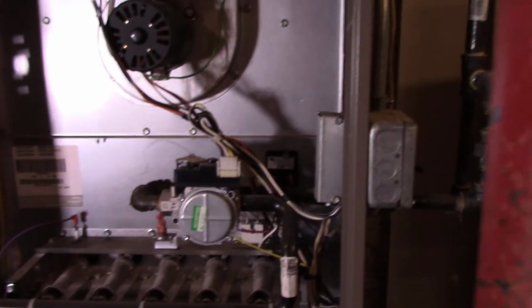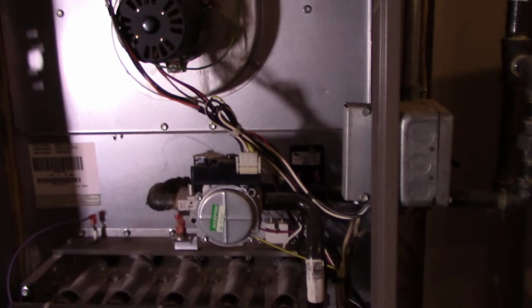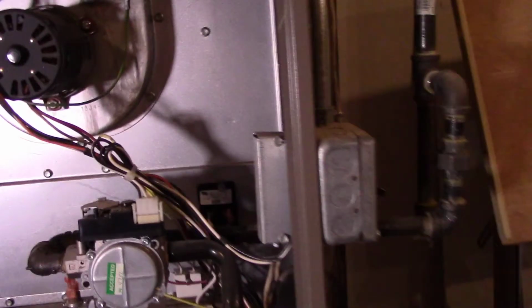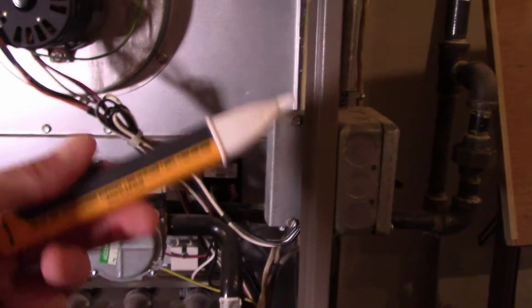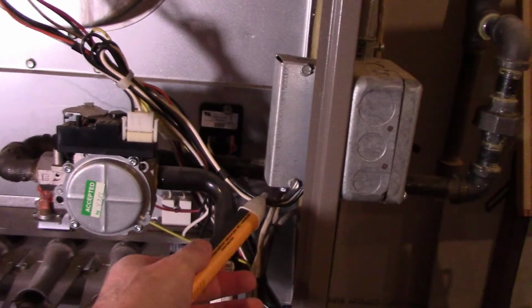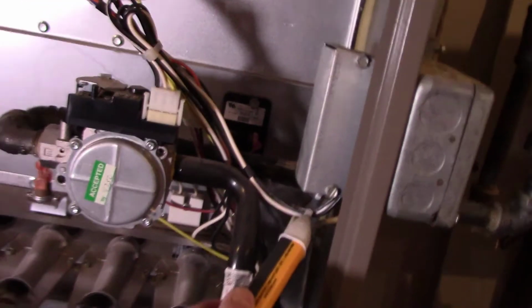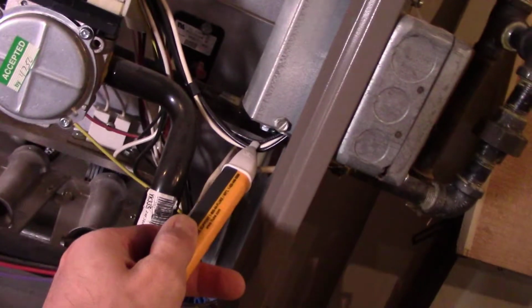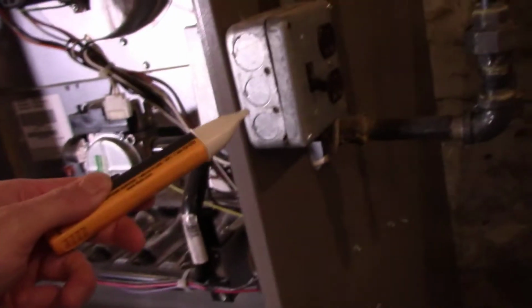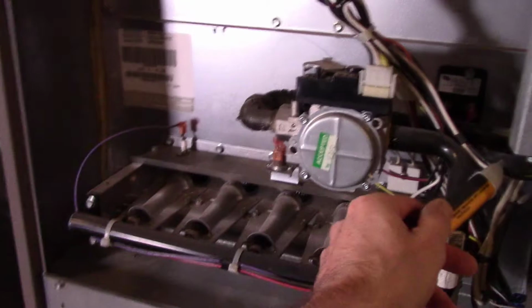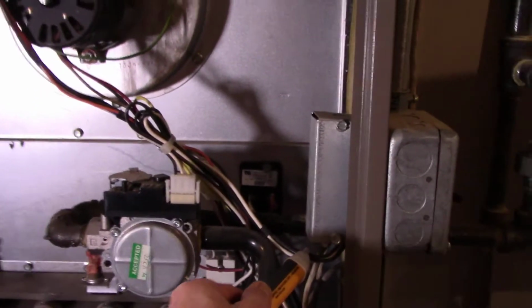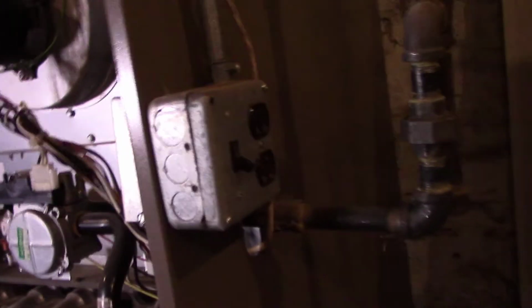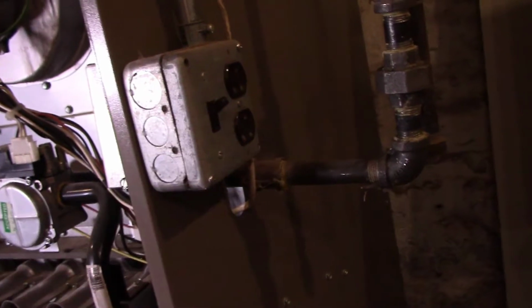Okay, now with the panel open, we can continue a little bit more troubleshooting with regard to our power here. So what we can do is take our voltage detector and see if we have power coming in from the wires here that are coming from the switch. As you can see, there is no power coming in, and that's because the easiest thing to troubleshoot is our switch is off.